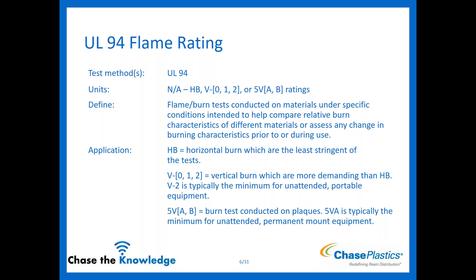What does that look like in application? HB stands for horizontal burn — it's the least stringent of those tests. Then you have your vertical burns: V0, V1, and V2. V2 at a minimum is generally used for unattended portable equipment. Then you have your 5VA and 5VB, conducted on plaques — the most stringent tests. 5VA is typically used at a minimum for unattended permanent mount equipment. I want to make sure we're understanding if there's going to be a requirement for these ahead of time.